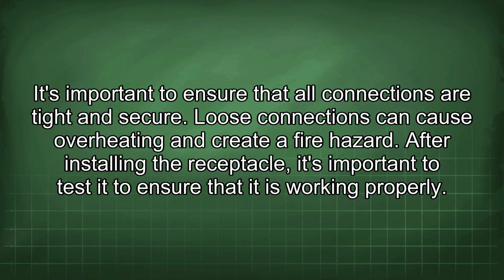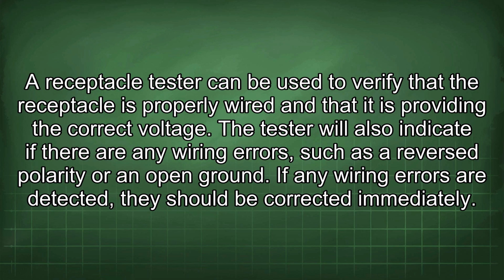After installing the receptacle, it's important to test it to ensure that it is working properly. A receptacle tester can be used to verify that the receptacle is properly wired and that it is providing the correct voltage. The tester will also indicate if there are any wiring errors, such as a reversed polarity or an open ground. If any wiring errors are detected, they should be corrected immediately.